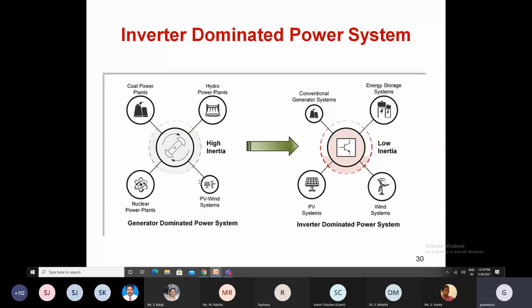The share of PV is less than 30% of load demand currently. But if PV's share exceeds 30% of load demand, the system becomes very low inertia. If a system has low inertia, even a smaller load change causes huge oscillations. If the system has higher inertia, even with a change in load demand, the system remains stable. The inertia is provided only by conventional generators—hydro, coal, or nuclear power. But PV provides very, very little inertia.